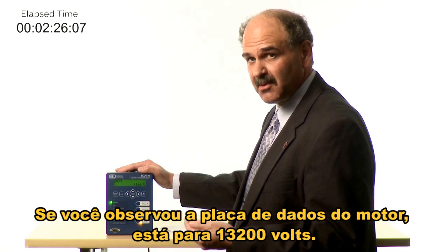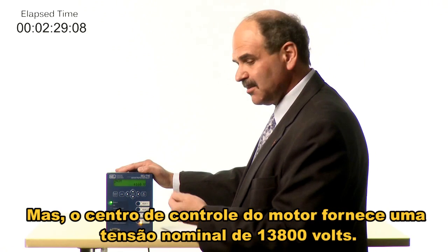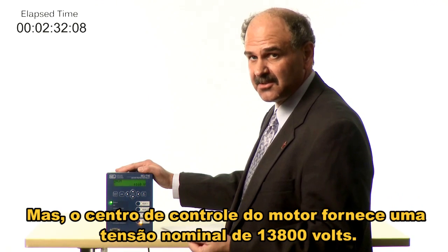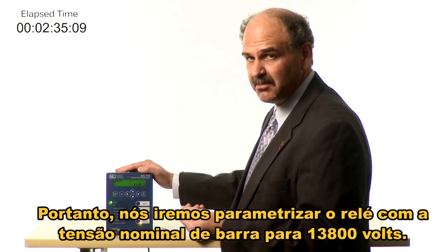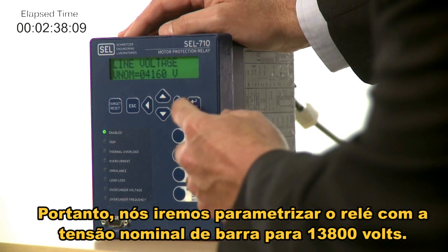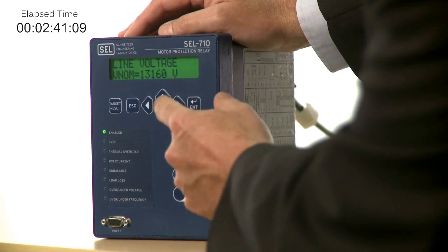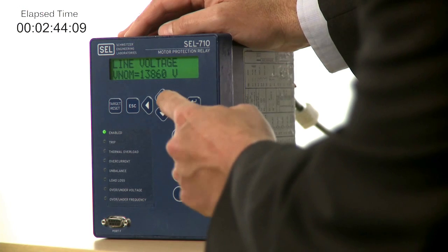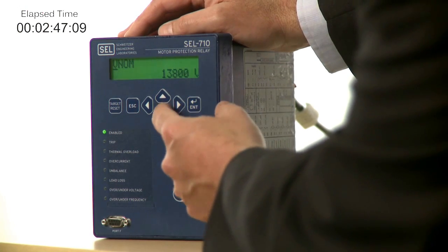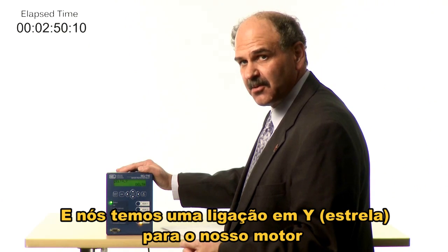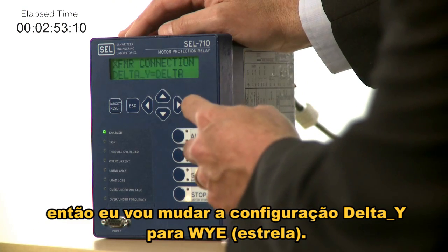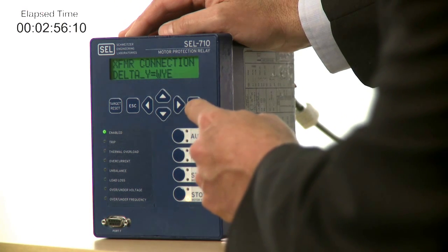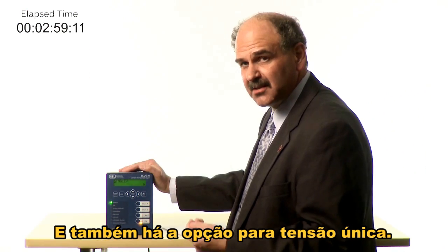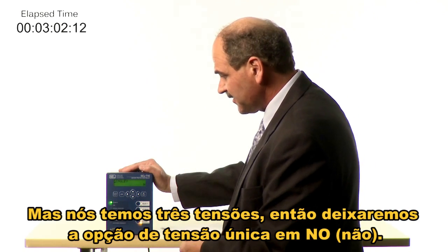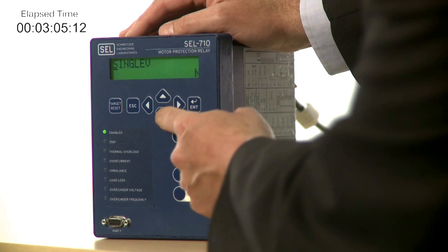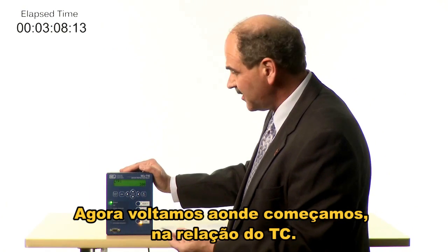Now if you looked at the motor nameplate, it was rated for 13,200 volts. But the motor control center supplies a rated voltage of 13,800 volts. So we're going to set the relay to the rated bus voltage of 13,800 volts. And we have a Y connection for our motor, so I'm going to change the delta Y setting to Y. This also has an option for a single voltage, but we have 3 voltages, so we leave the single voltage set at no. So now we're back to where we started on the CT ratio.